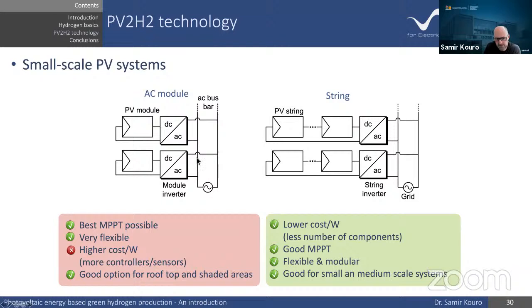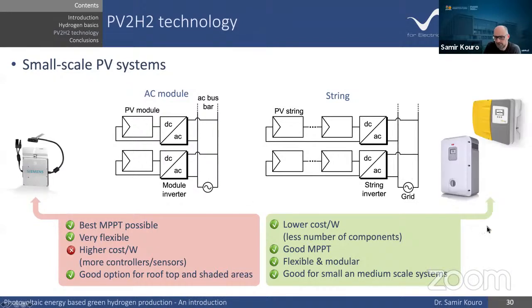just as a single stage, it's basically a 2-stage because you have a very low voltage over here and you have grid voltage over here, so you have to boost. And inverters don't actually boost, so you first have to have a boost stage of some sort. You can have isolation, so you can use a transformer to boost in the DC-DC stage, and then you have a buck inverter to reduce to the grid, right? So these are usually used for small systems, the same as with the string inverter.